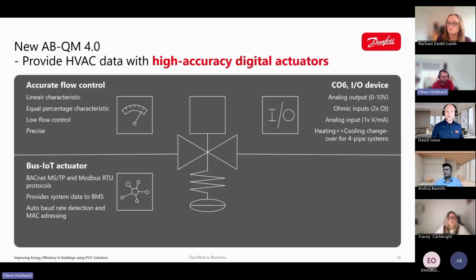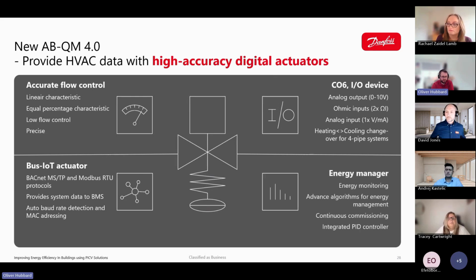So for flow control and valve characteristics, it ensures accurate flow control with linear and equal percentage characteristics. It also supports low flow regulation and delivers precise performance across all operating conditions. It's compatible with the BACnet and Modbus RTU protocols, providing real-time system data to the BMS system. And you've also got analog outputs of 0 to 10 volts, ohmic and analog inputs, and heating cooling changeover for a 4-pipe system. It also monitors energy usage and applies advanced algorithms for optimized energy management, and it supports continuous commissioning and includes an integrated PID control for precise system regulation.